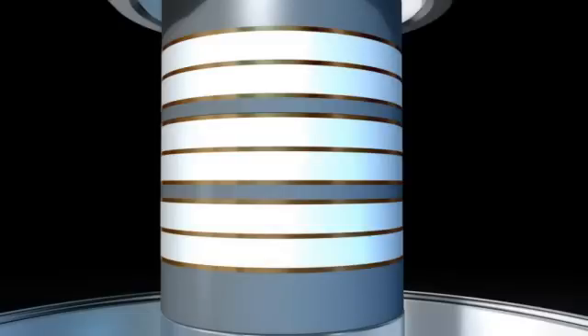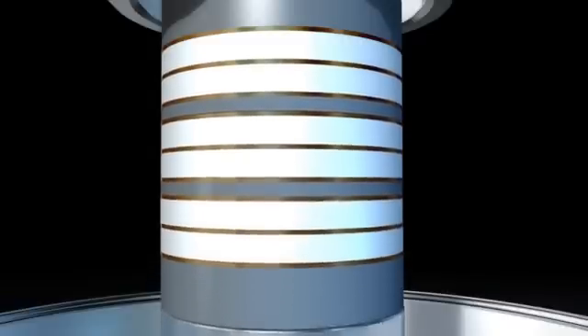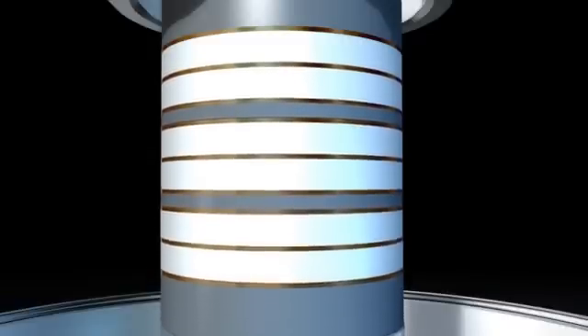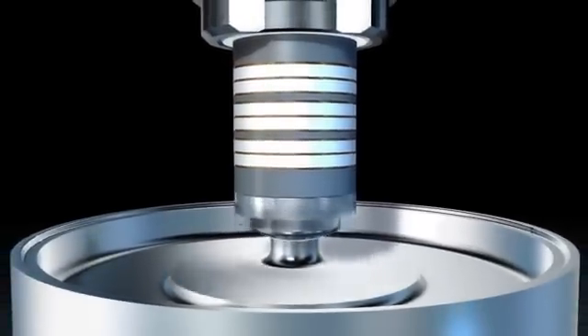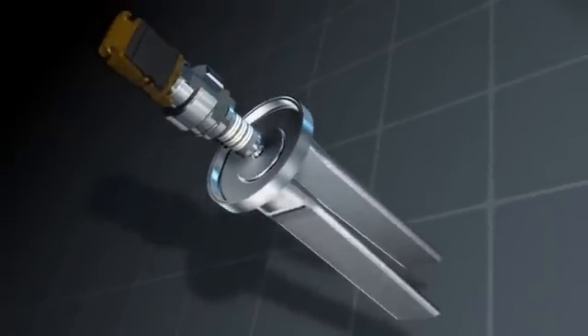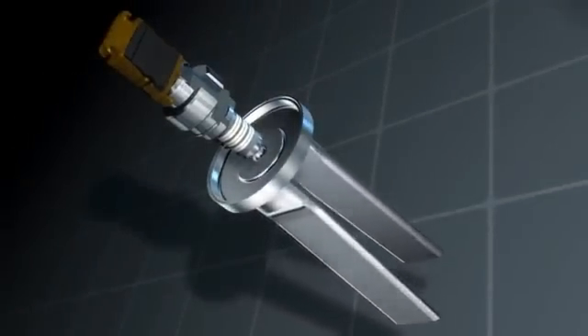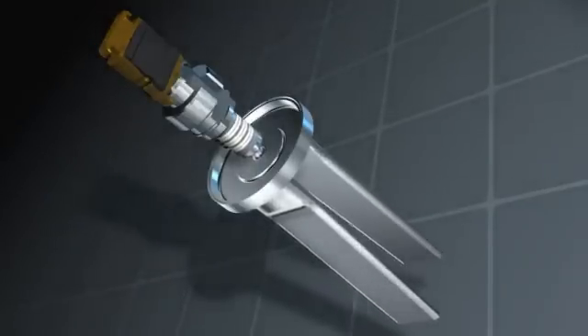The stack drive, however, stacks and fixes several piezo disks with changing polarization on top of each other. The application of a respective alternating voltage also causes the piezos to oscillate. As the piezos expand, the membrane is bent to the outside. The ends of the tuning fork, which is attached to the membrane, are pushed apart. As the piezo contracts again, the membrane is bent to the inside. The ends of the tuning forks, attached to it, are pulled together.